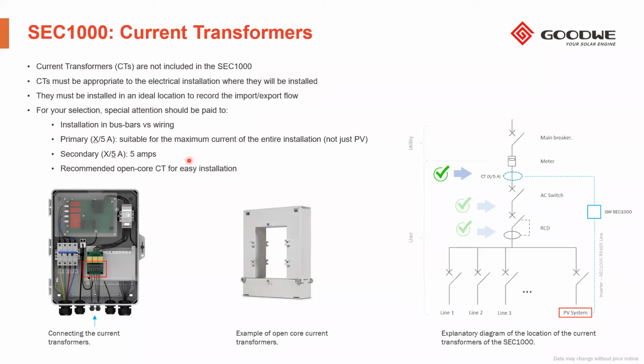In this example, the primary has to be suitable for the maximum current of the installation, including the PV, but not only PV, right? So it has to measure everything. And the secondary has to be 5 amps, because this is what the SEC 1000 can read, right? It's the standard one, by the way. We recommend open core CTs. Basically, open core means that you can dismount this part of the CT and build it again once you insert the main body in the bus bar or in the wiring. That gives you the chance to install the CT without any intervention in the electrical facility, right? Otherwise, if you use a closed core CT, you need to dismount the existing electrical cabling and bus bar, etc. What is not really recommended. That's not very smart.